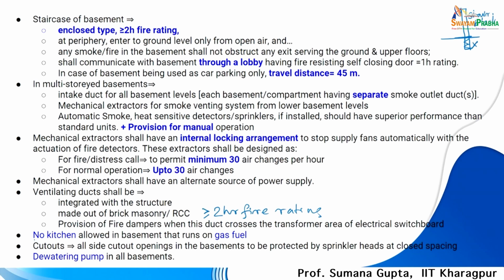Here you see, as I have talked about services, there should not be any kitchen kind of services which run on gas fuel. So, no kitchen or support service should be provided which runs on gas, fuel or oil. Dewatering pumps should be there in all basements, because in case of firefighting, water can come into these areas and make the place waterlogged. So the dewatering pumps should operate and take out the water which may accumulate in case of fire, and it should be easily drained out.